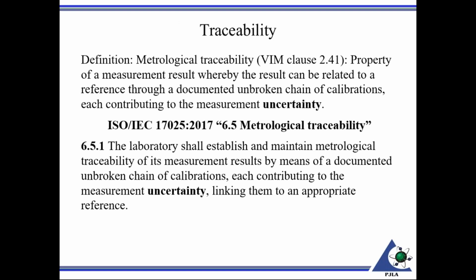So I want to bring up the term traceability here. Of course, we have requirements in the standards concerning traceability. However, it does intertwine with uncertainty. Traceability is sometimes a term that gets tossed around loosely, but it has a defined meaning. From the vocabulary of international metrology, metrological traceability is a property of a measurement result whereby the result can be related to a reference through a documented, unbroken chain of calibrations, each contributing to the measurement uncertainty.